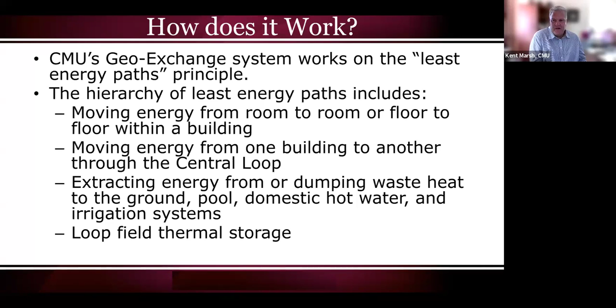One of the reasons we decided back in 2007 to install a thermal energy network was because it's very cost effective. Heat pumps are very efficient—in fact, the coefficient of performance of our system at certain times of the year exceeds 8. A study by our local utility provider analyzed the coefficient of performance of our system: over the summer it's as high as 6, and in parts of the winter it's as high as 8.